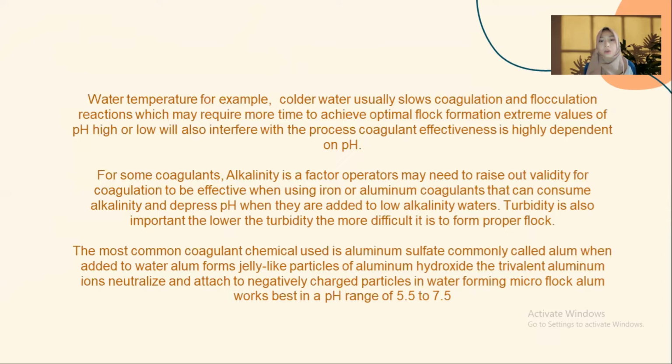When using iron or aluminum coagulants, they can consume alkalinity and depress pH when they are added to low alkalinity waters. Turbidity is also important. The lower the turbidity, the more difficult it is to form proper floc.